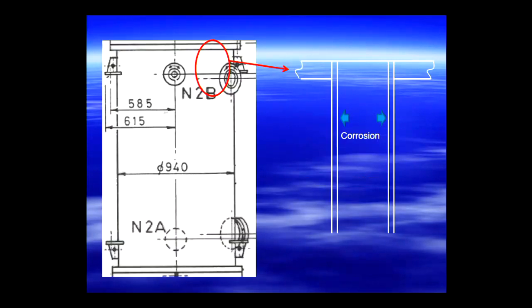Here's the reason. Now, if I zoom in on a little detail of where one of those tubes is welded to the top tube sheet. There's a level of acetic acid in that tube, which comes to around about 100 mil from the top of the tube. As the steam condenses outside the tube, it conveys heat into the other liquid, into the glacial acetic acid, which boils it.